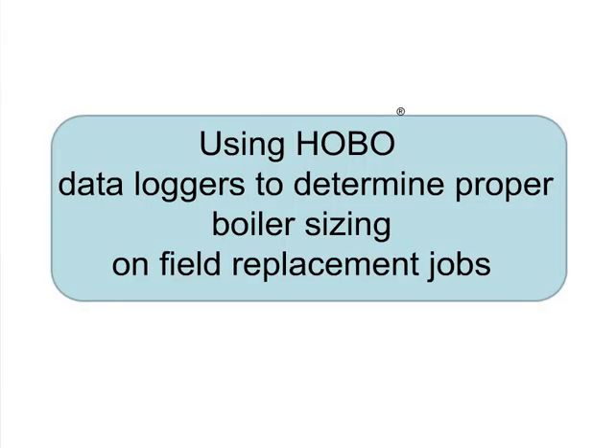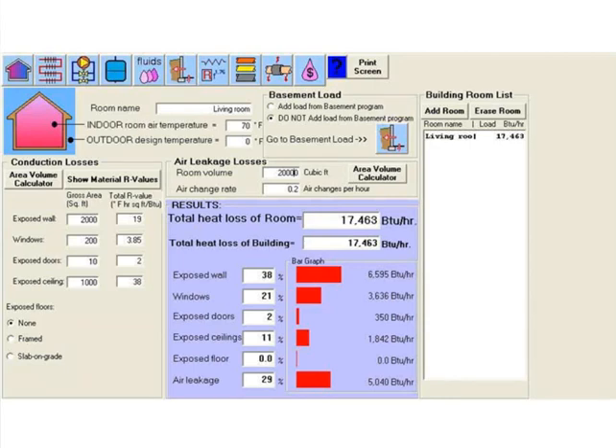I'm coming to you today to talk about the intricacies of properly determining the right size of a replacement boiler for an existing building. A person could perform a detailed heat loss calculation, but in my experience even on jobs that I know are properly sized, when it gets real cold outside — down to design condition — the heating system is only running at 50% of its capacity. This indicates the heat source is twice as large as it needs to be, resulting in wasted fuel and excess wear and tear from frequent starting and stopping.